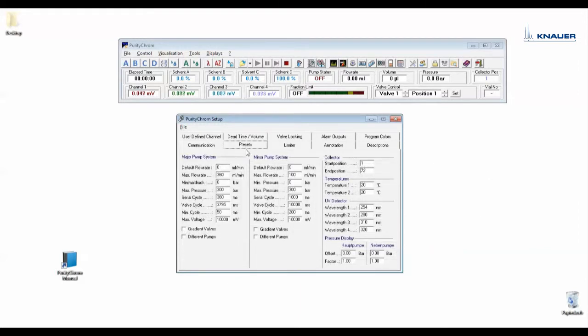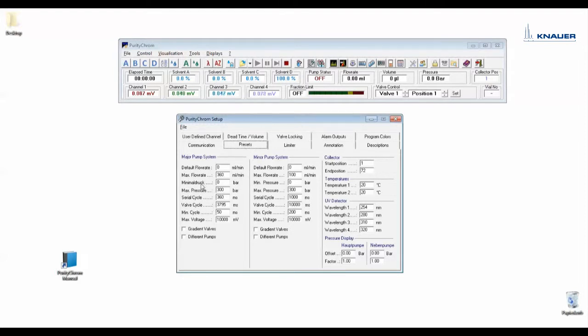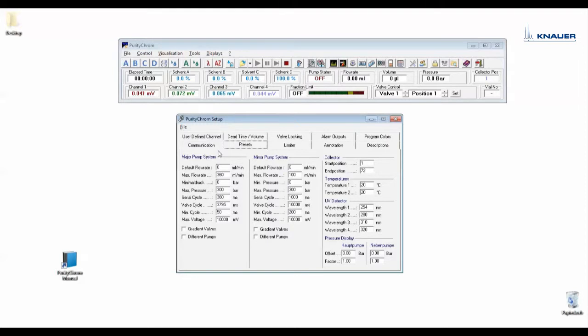Under presets you can set the presets for your major pump system or the minor pump system. For example, you can set here maximum pressure and a minimum pressure or the default flow rate. I would recommend to enter here a zero for the default flow rate because after saving the setup the pumps will start with the entered flow rate here.